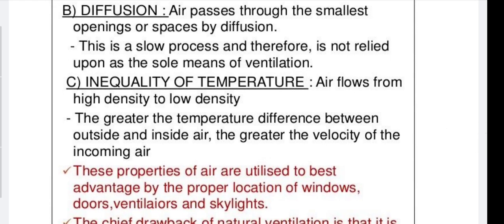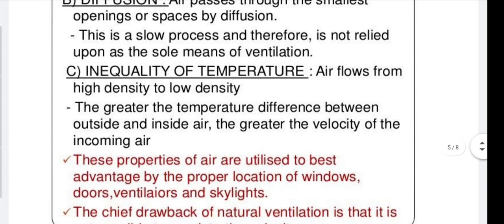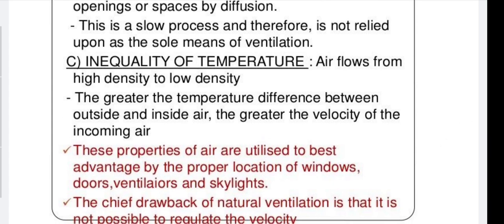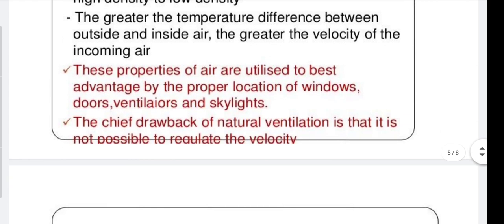Third mechanism is inequality of temperature. Air flows from high density to low density, and from high pressure to low pressure areas. The greater the temperature difference between outside and inside air, the greater the velocity of incoming air. These properties are utilized by the proper location of windows, doors, ventilators, and skylights. The chief drawback of natural ventilation is that the velocity cannot be regulated.